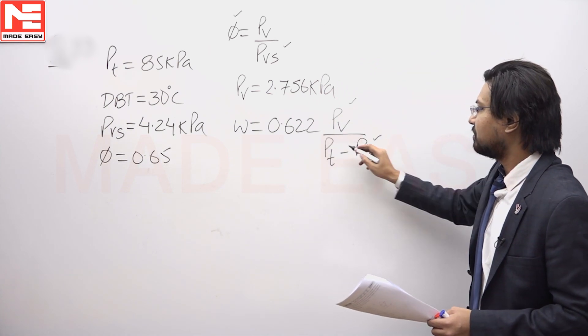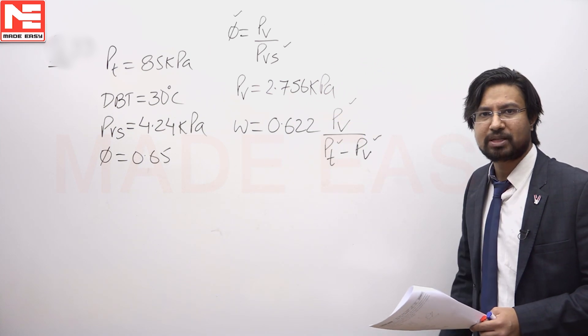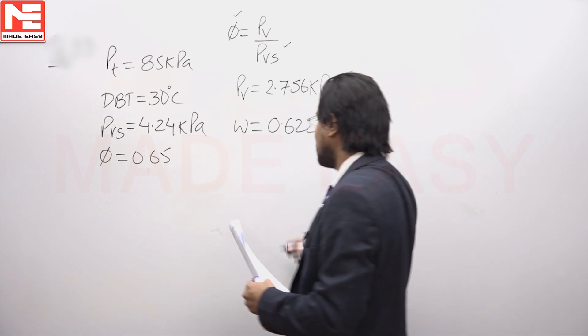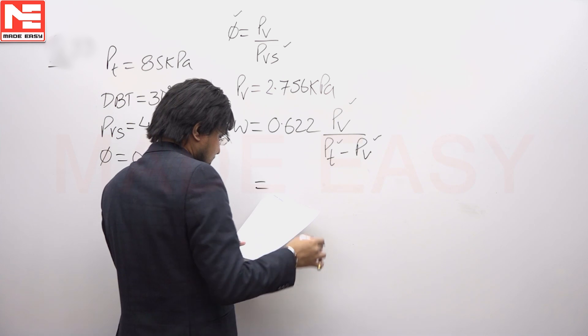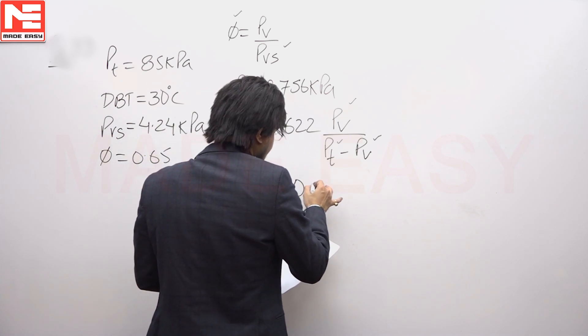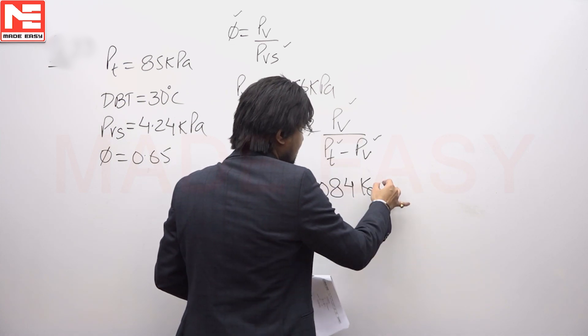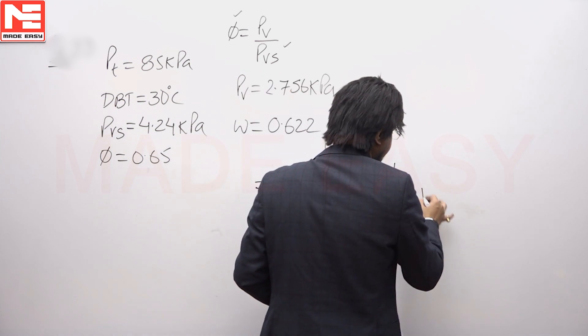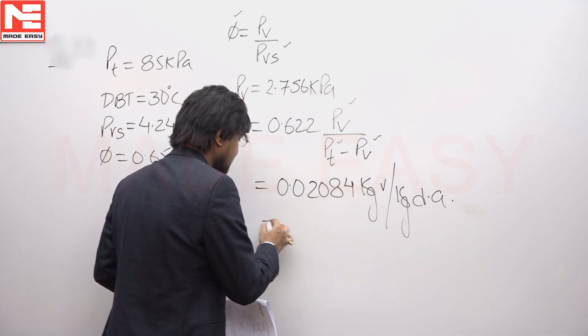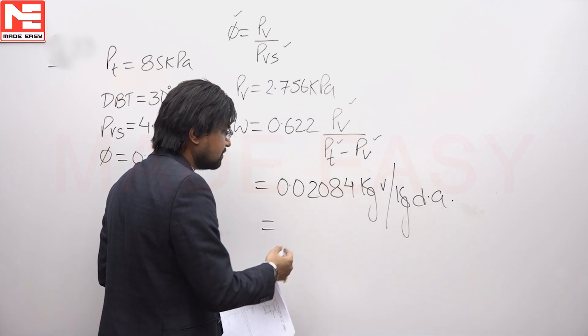Pv we have found out, Pt is given to us as 85 kilopascal. Using this data, I will find out the value of omega. Omega comes out to be 0.02084, but this will be in kilogram of vapor per kilogram of dry air, and I have to convert it into grams as asked in the problem.